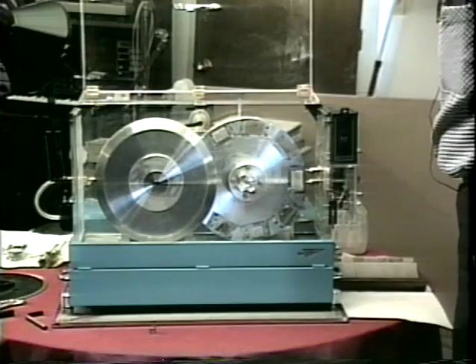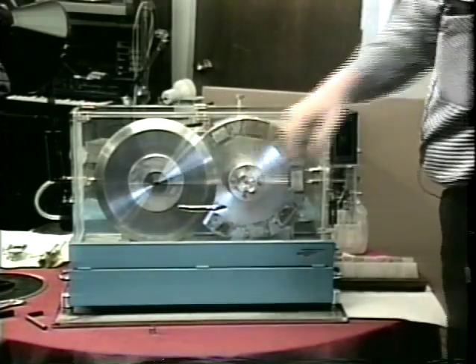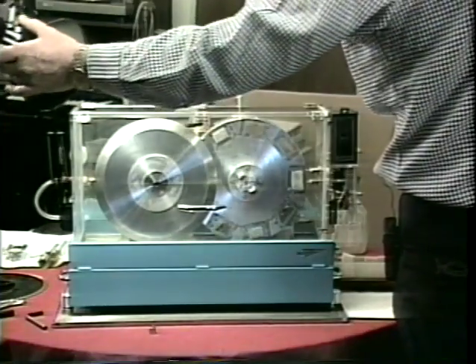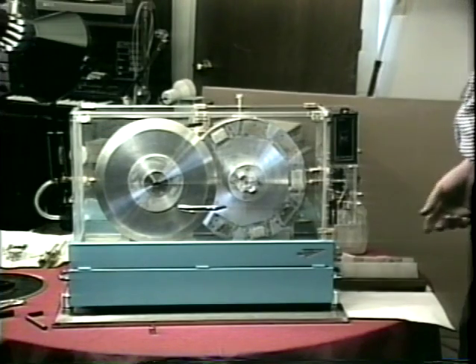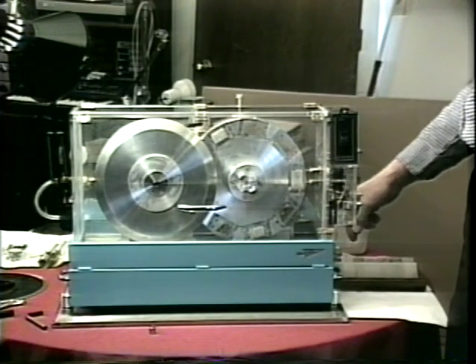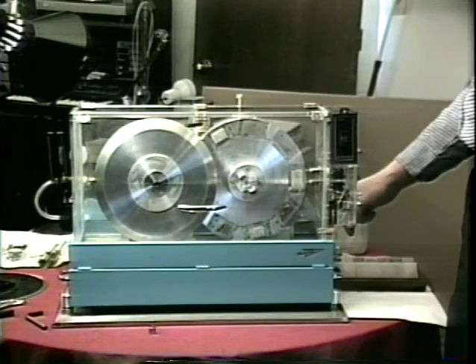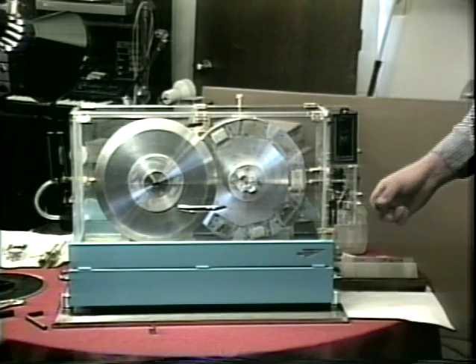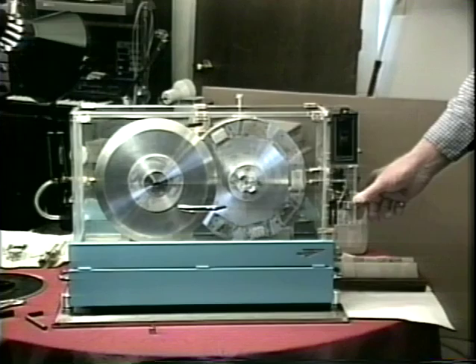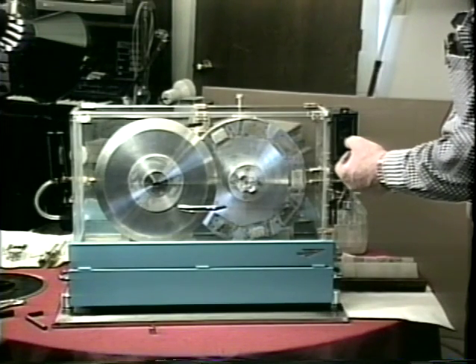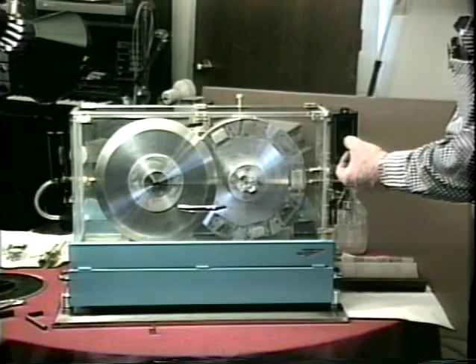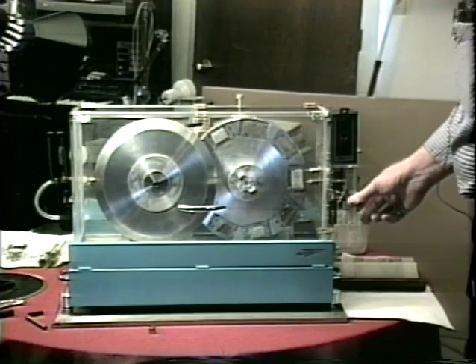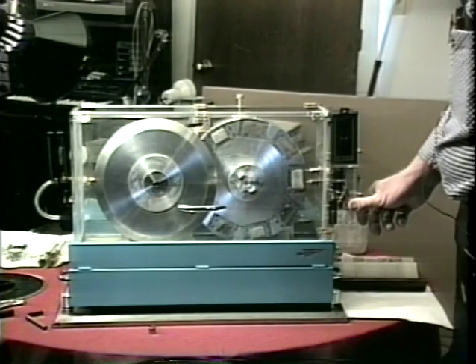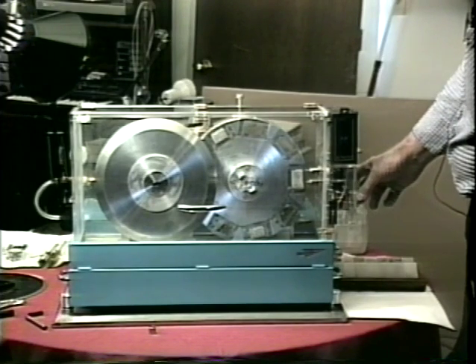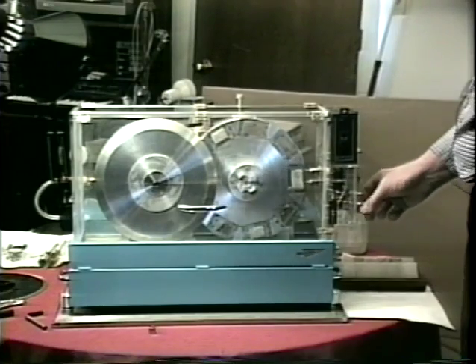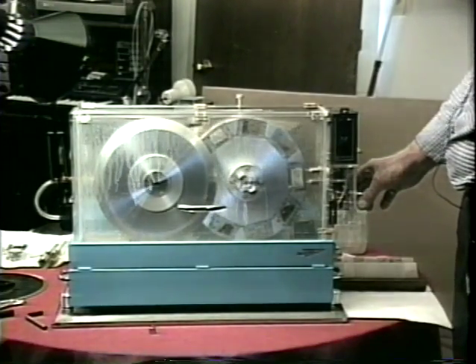Begin the cycle by closing the coolant shield door. We'll put some illumination on here by turning on the machine lamp. We'll go to the control panel and set the spindle speed to the low speed for grinding. Then we'll set the rapid travel switch to off. Go to the predetermining counter and set it for 02, which is 2 machine cycles or 2 passes by the diamond plate. We'll pull the cycle reset switch forward for counter reset, and then we'll push it all the way back in order to get the start of the cycle. That initiates the grinding operation.